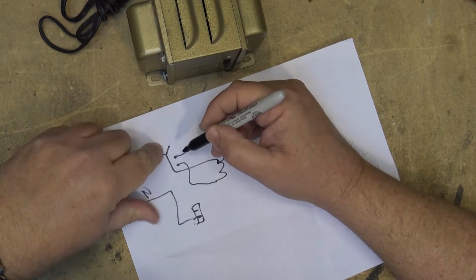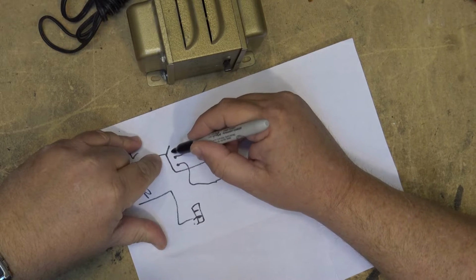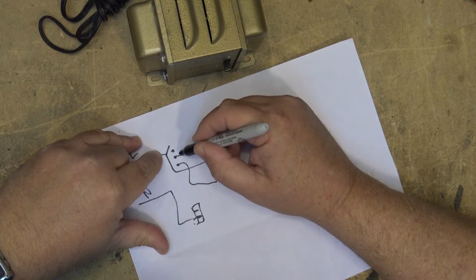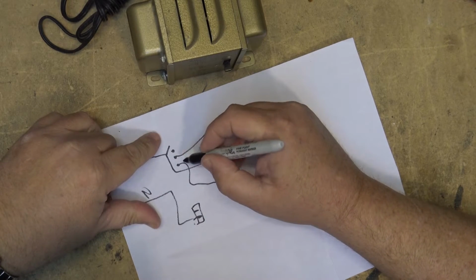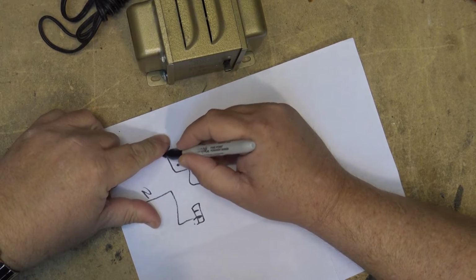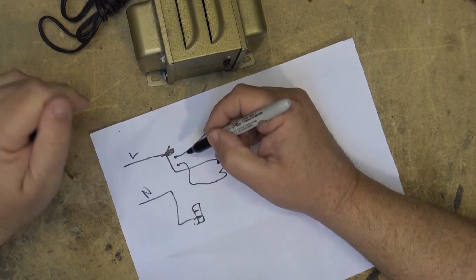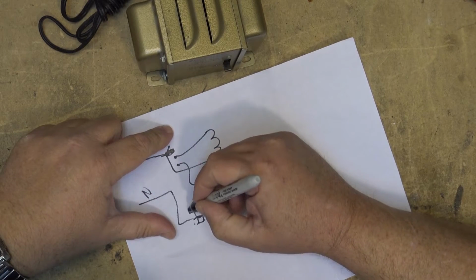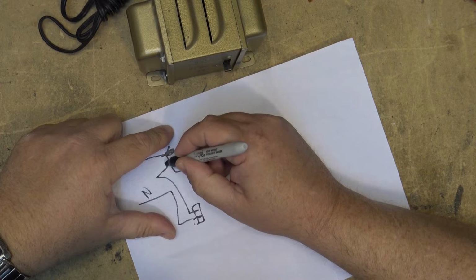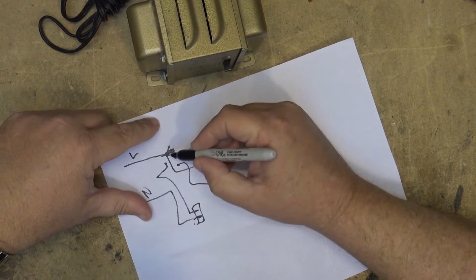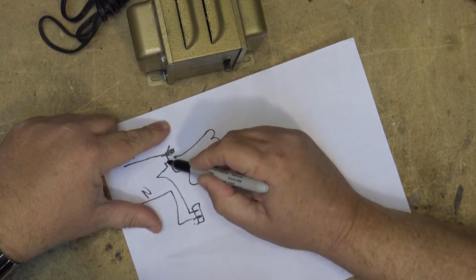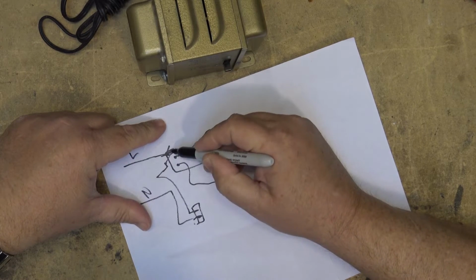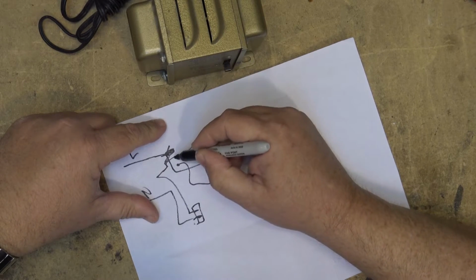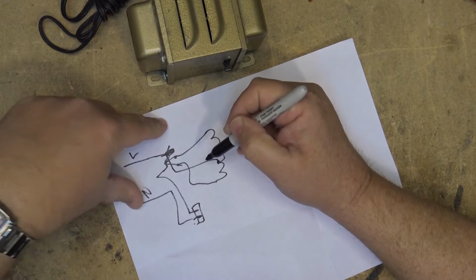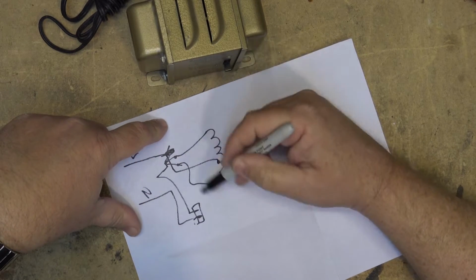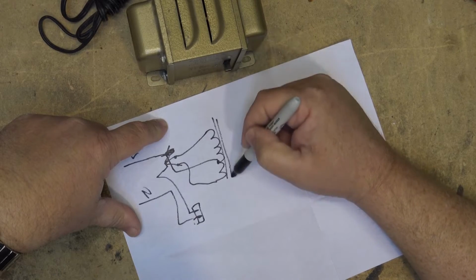The switch itself is able to switch between 3 different terminals. Actually, I drew this wrong - this should be going to the terminal here, not to the wiper. The wiper goes to the line. So in the normal off position, it's open. In the normal position, it's connected to the line, in the boost position it's connected to one, and in the drop position it's connected to the other. That's how this works. There's no isolation whatsoever - this is just a coil.